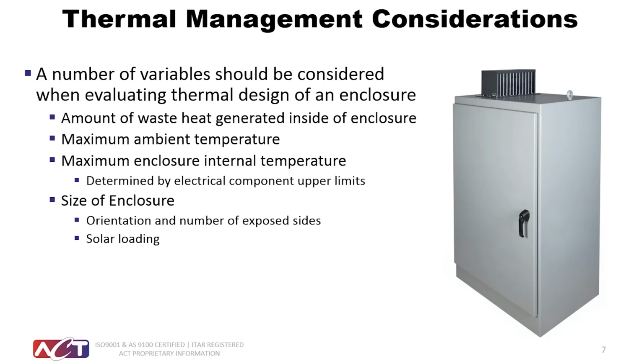There are a number of variables to consider when evaluating what type of thermal management an enclosure will need. It is helpful to know the amount of heat being generated inside of an enclosure, as well as the operating environment, specifically the maximum ambient temperature and whether or not there will be a direct solar load on the outside of the cabinet. Each component should be examined to determine the maximum temperature that it can tolerate, which will drive the allowable air temperature inside of the enclosure.